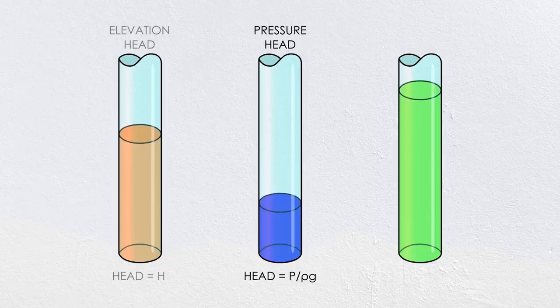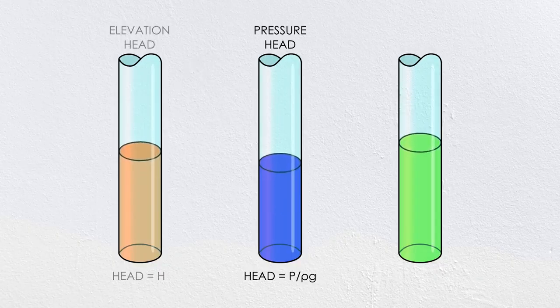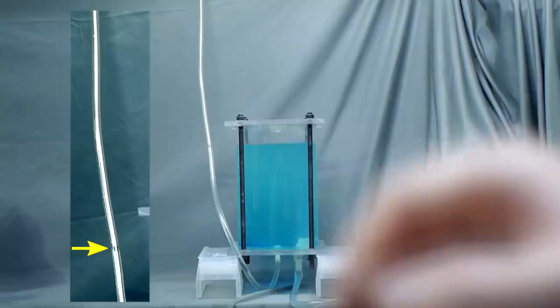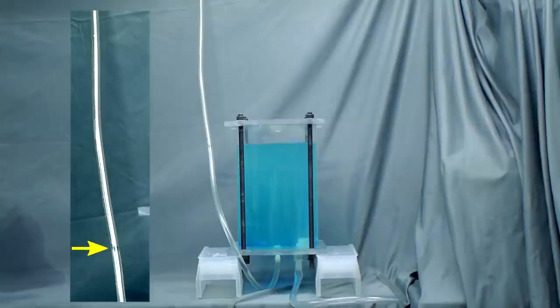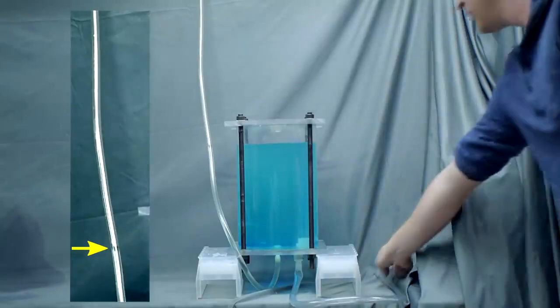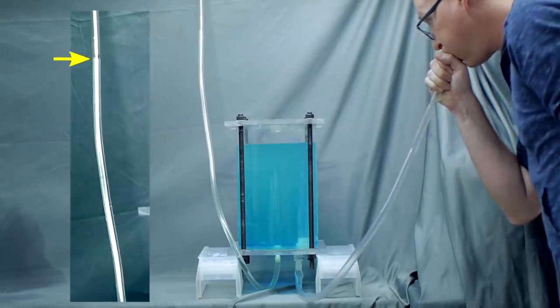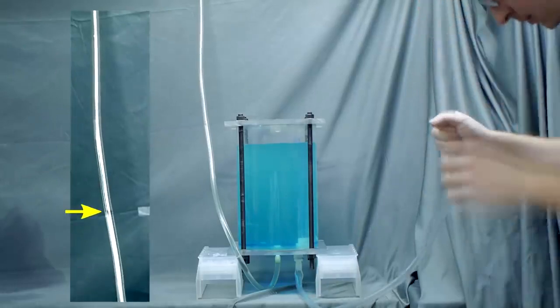The second type of energy is pressure head. In this case the head is the pressure divided by the gravity times the density of the fluid. So if I close off the top of my tank and add some air pressure, the level in the tube goes up. The new height is the pressure head, the equivalent static column related to the pressure in the tank.